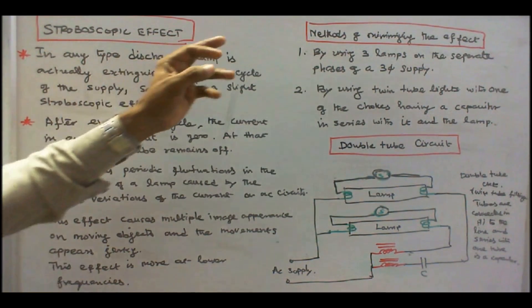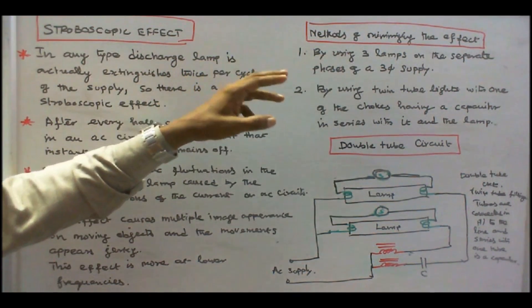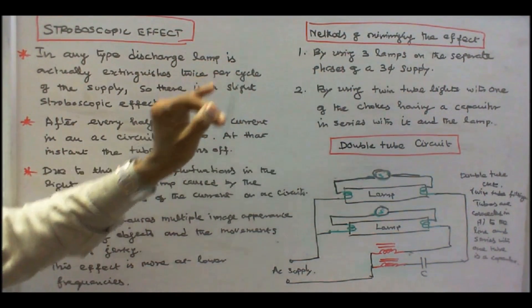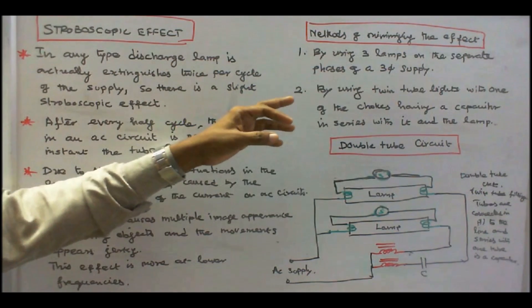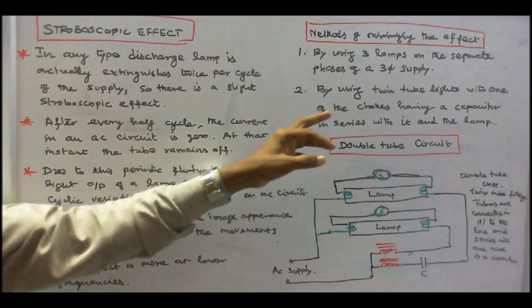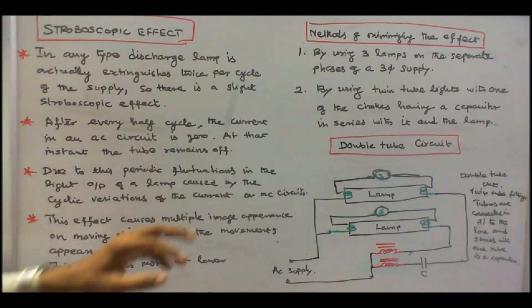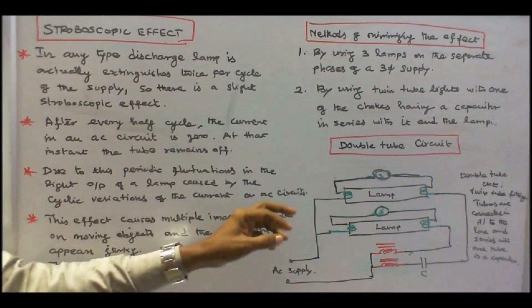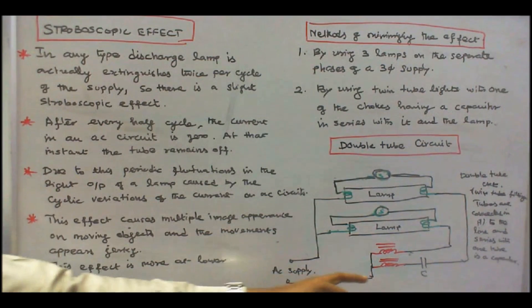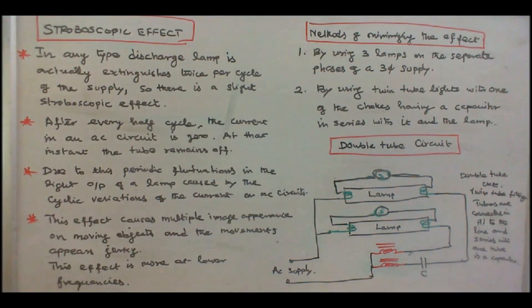The next is methods of minimizing the stroboscopic effect. Number 1, by using 3 lamps on the separate phases of a 3-phase supply. Number 2, by using twin tube lights or double tube lights with one of the choke having a capacitor in series with it and the lamp. So this is the double tube light circuit. Here the tubes are connected in parallel to the line. And in series with one tube is a capacitor. Here this is a capacitor C. So this is the arrangement. In many industries, they are using twin tube lights. The reason is to minimize the stroboscopic effect.